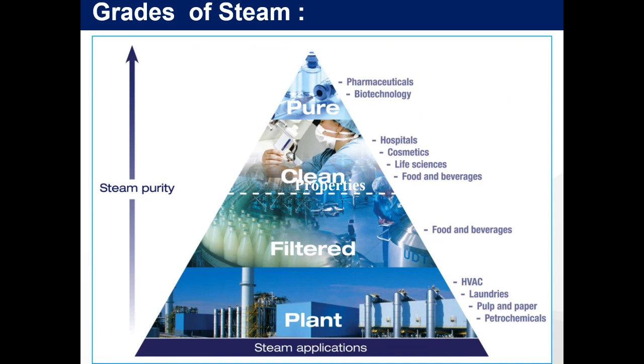Then we move to filtered steam, which we also call culinary steam. This is for the food and beverage process. Any of you that work for the breweries or in the food industry will be familiar with our filter units, after which all the pipework will change to stainless steel so that you can remove any corrosion, erosion. Then clean steam, which is for hospitals, cosmetics, life sciences, food and beverages again, more for where steam is in contact with a product, because steam is then an ingredient of those products. And pharmaceutical, so ultra pure, ultra clean steam systems, high filtration, demineralized water systems.